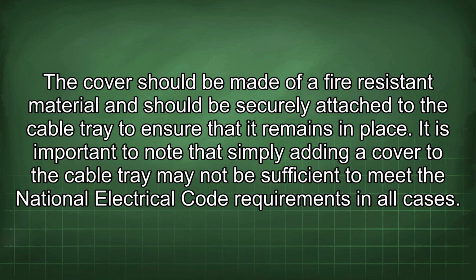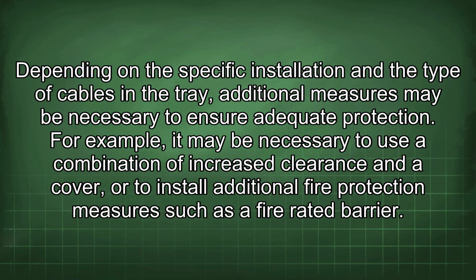It is important to note that simply adding a cover to the cable tray may not be sufficient to meet the National Electrical Code requirements in all cases. Depending on the specific installation and the type of cables in the tray, additional measures may be necessary to ensure adequate protection. For example, it may be necessary to use a combination of increased clearance and the cover, or to install additional fire protection measures such as a fire-rated barrier.